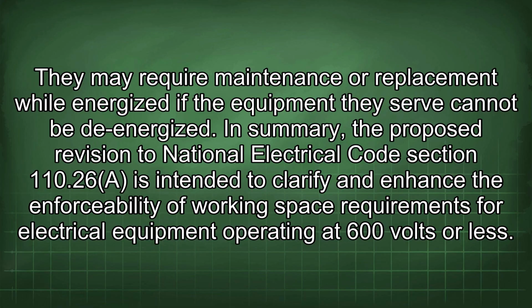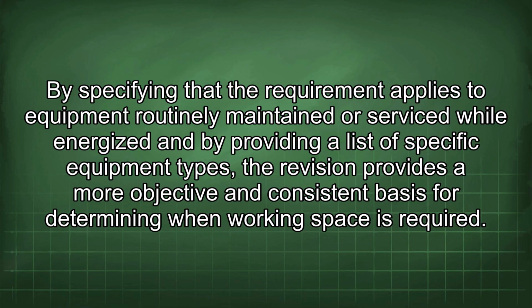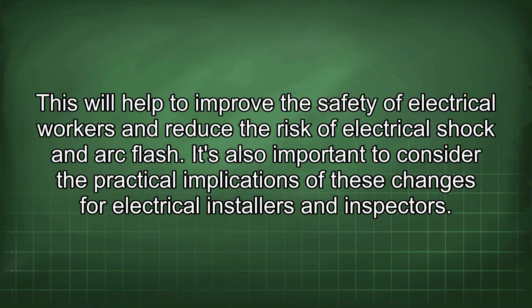In summary, the proposed revision to National Electrical Code Section 110.26 is intended to clarify and enhance the enforceability of working space requirements for electrical equipment operating at 600 volts or less, by specifying that the requirement applies to equipment routinely maintained or serviced while energized, and by providing a list of specific equipment types. The revision provides a more objective and consistent basis for determining when working space is required. This will help to improve the safety of electrical workers and reduce the risk of electrical shock and arc flash.